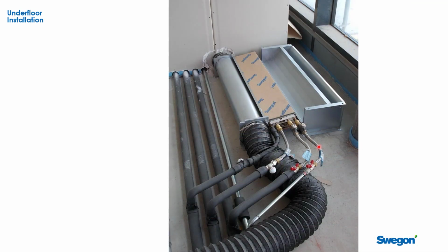This is an underfloor application in here, so you've got the lines on the floor. You can see they've been insulated in here. We've got shut-off valves and then flex hoses over to the coil. This is a 4-pipe coil, and the air is underneath the floor, drawn through this coil. This is the primary air. The nozzle bank is actually right along there and creates a low pressure area underneath the coil that draws the air that's coming from the room into the floor plenum, and then is delivered back through this slot here, back up through some form of slot diffuser in the raised floor.